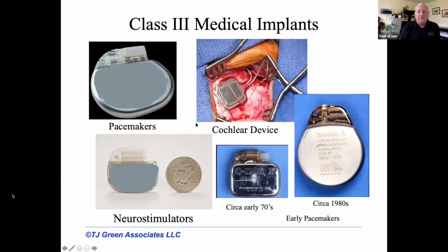But you can see here, our focus is Class 3 products. A Class 3 device is one whereby if it were to fail, it could put the patient at risk. The ones most people are familiar with are pacemakers, cochlear implants, and neurostimulators, which are very common. Even to this day, a lot of them are hermetically sealed in titanium cans, even though there's a lot of work and interest in developing non-hermetic implanted products, just as they are in the MIL community, looking at non-hermetic solutions. One of the things you'll notice about some of these devices is they all have a molded or plastic header encasing the hermetic feedthroughs. That's something that can be a problem if you're going to do leak tests.